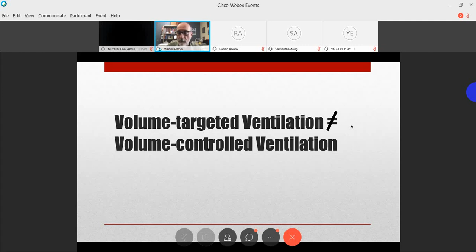So this is another way of looking at the differences. There are differences in terms of the gas flow. With pressure-controlled ventilation, again, we set the pressure, and that pressure results in a certain flow, and that flow results in a certain tidal volume. And again, when compliance changes, that delivered volume will change. With volume-controlled ventilation, there is a continuous flow of gas into the circuit until the set tidal volume is delivered, and pressure rises passively, reaching peak just before expiration begins. Pressure is therefore the dependent variable. There's some pressure limit, usually set at 45 or so. So it's a different gas flow pattern.